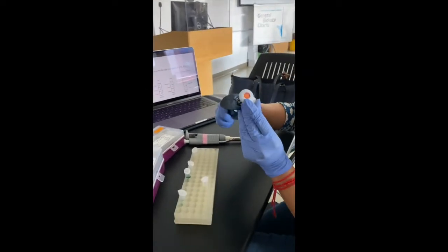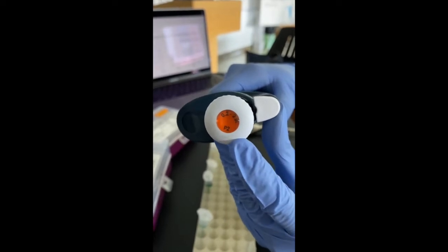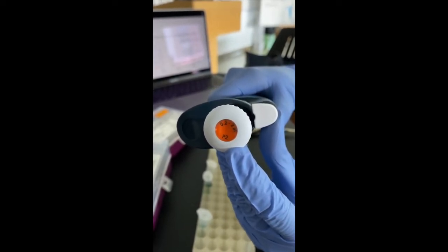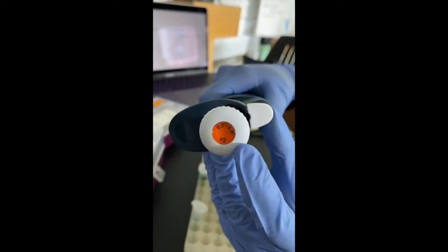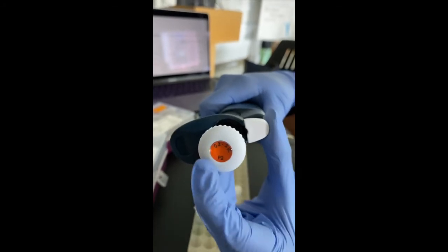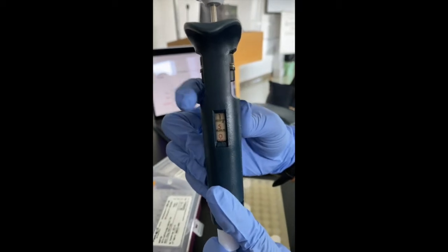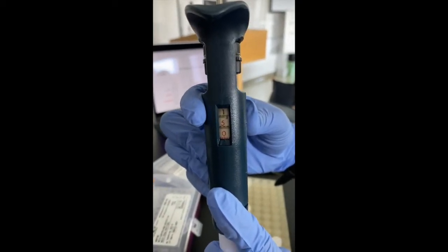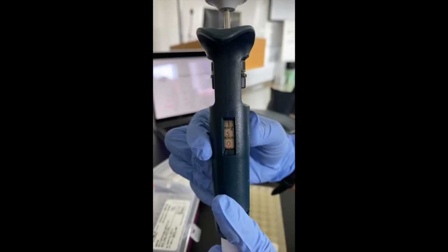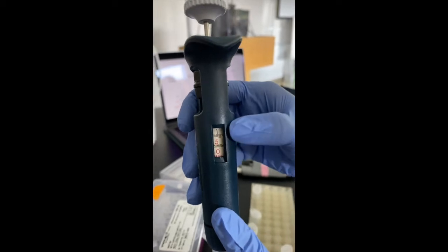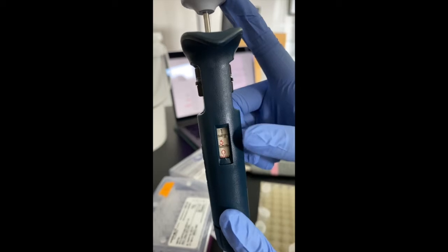The first one, as I mentioned in the lecture, is P2. The name of the pipette has a number which indicates the maximum volume it can be used to measure. So P2 has a range of 0.2 microliters to a volume as large as 2 microliters. So this is the plunger and this is the volume indicator window. For P2, the first digit on the window indicates the ones digit, and the second and the third digits indicate the first and the second digits after the decimal point.